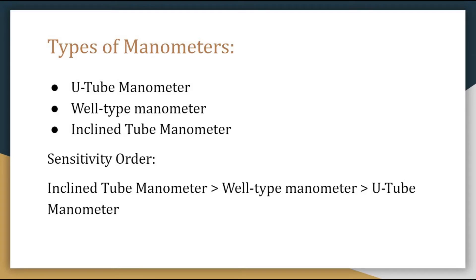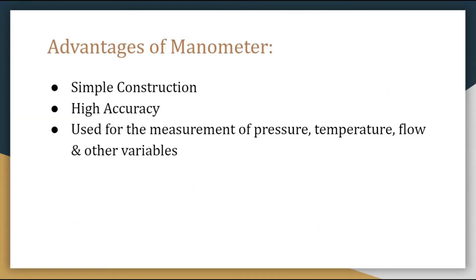Moving forward, the types of manometers we have are: U-tube manometer, well type manometer, and inclined tube manometer. The sensitivity order is: inclined tube manometer has the highest sensitivity, then well type manometer, and U-tube manometer has the lowest sensitivity among these three. The advantages of a manometer are: it is simple in construction, gives high accuracy, and along with pressure it is used for measurement of temperature, flow, and other variables as well.